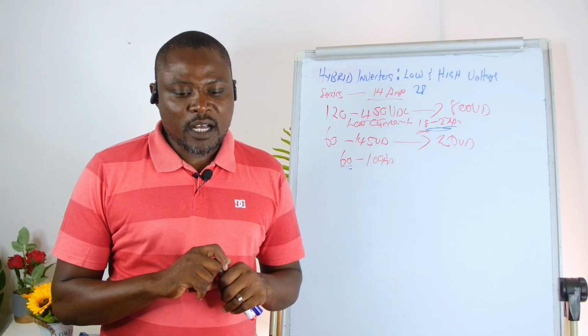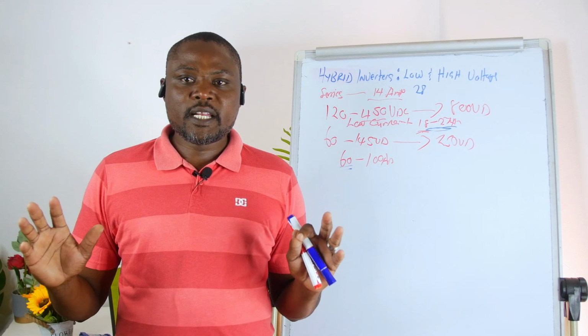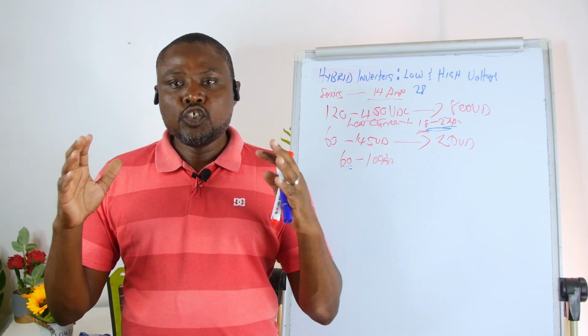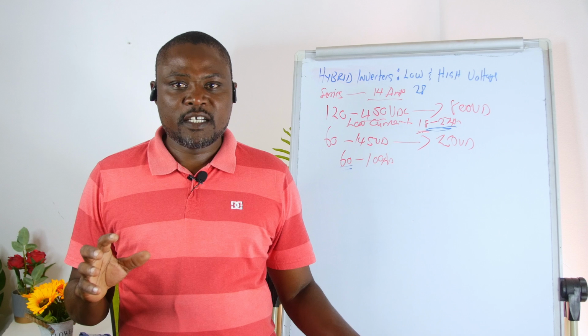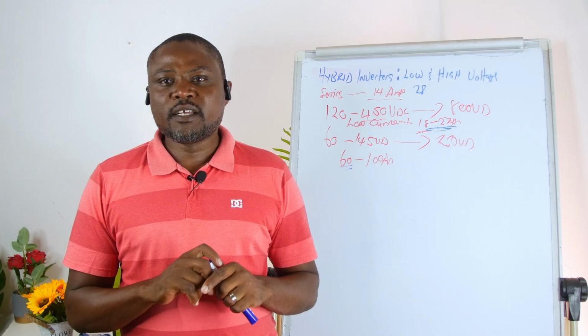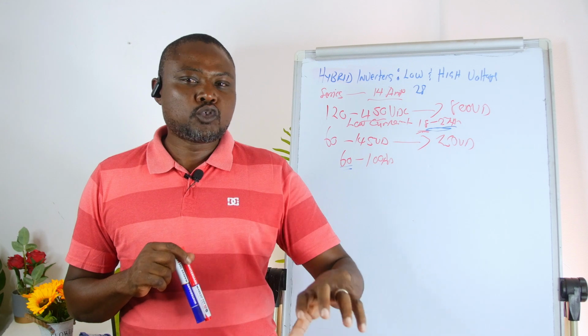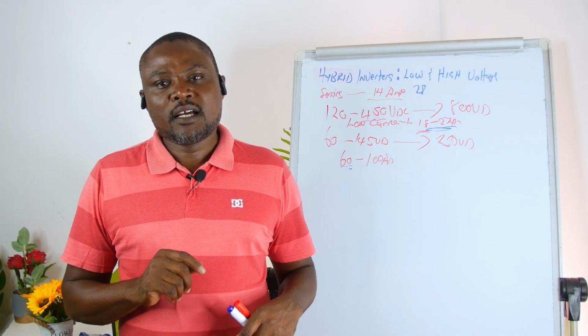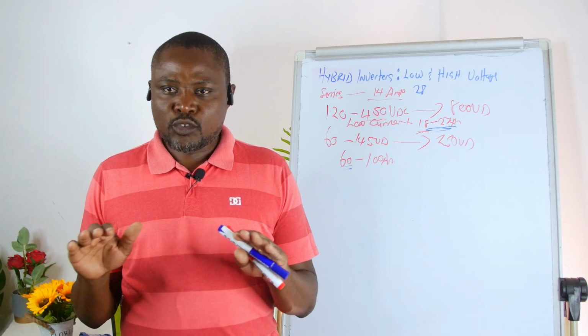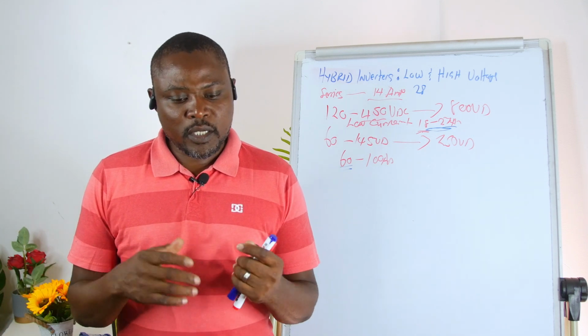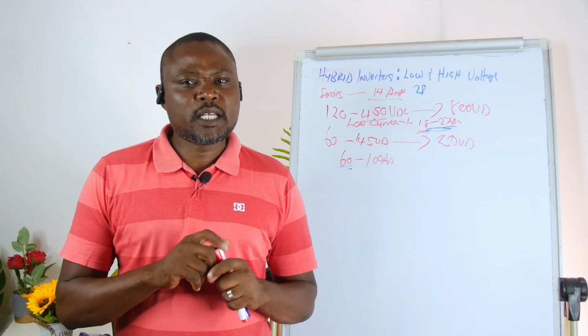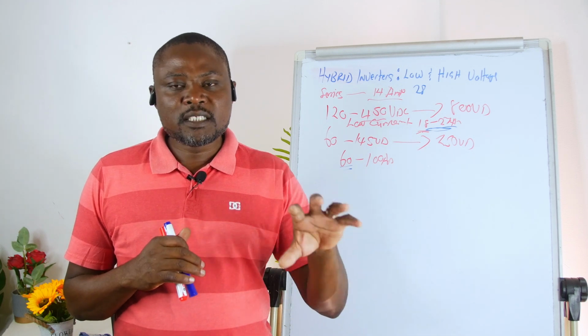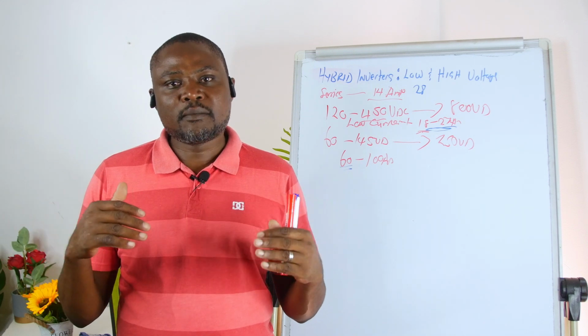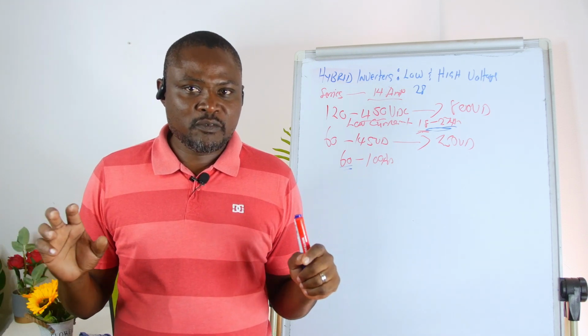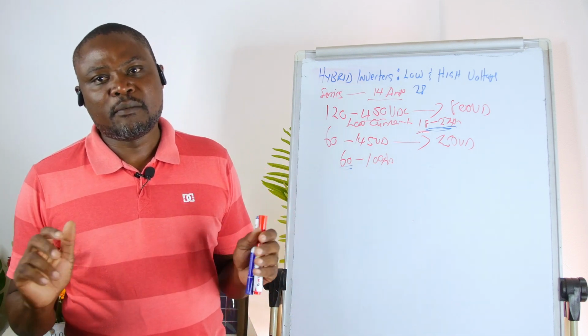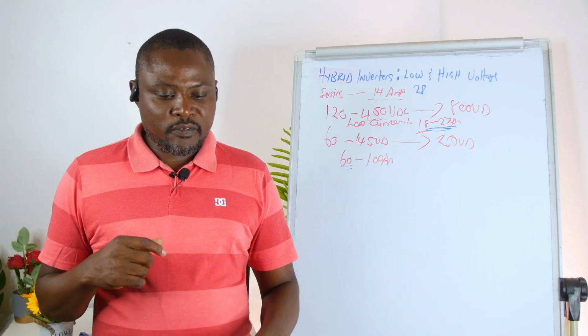Then there's direct power usage for solar. With high voltage, you can literally use your solar array during the day without the battery. The configuration, even on the inverters, allows you to switch off the batteries and still get solar to power your loads during the day. That works perfectly fine, so it's a good option to consider. Whereas with low voltage, if you remove the battery component, the system will begin to act up and won't be able to work. But with high voltage, most inverters work without a battery switched on, which is a very good advantage to consider.